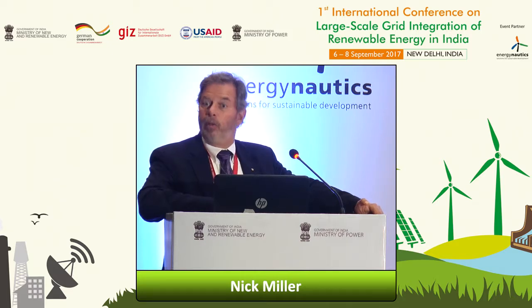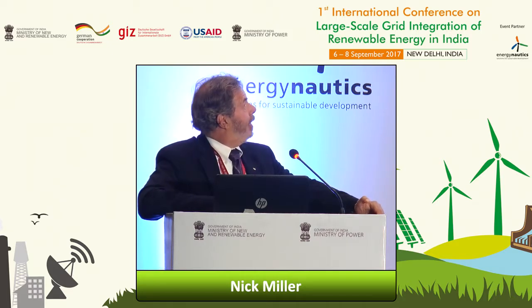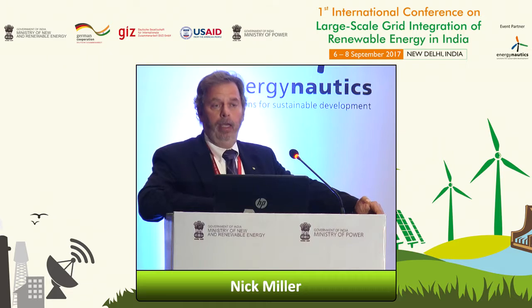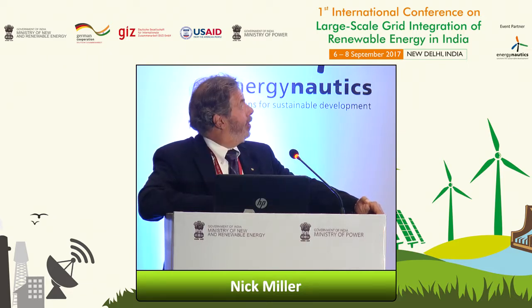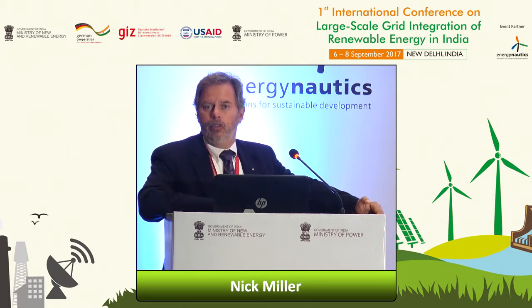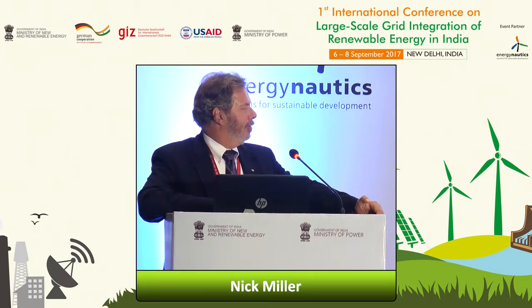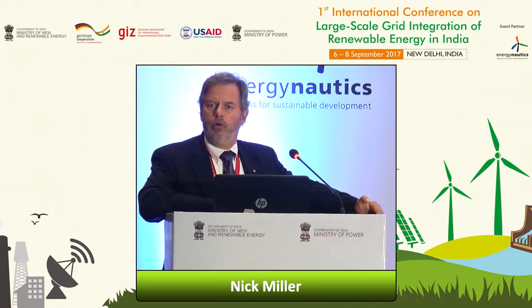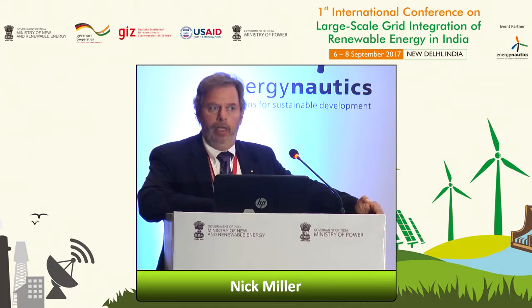So the 162 megawatt plant is pretty big. It's connected by a radial 75 kilometer 230 kV transmission line to a line that is radially connected by another 100 kilometers to the rest of the grid. So this is out in the middle of nowhere, and the requirement was for voltage control to manage the variation that came with the wind speed.